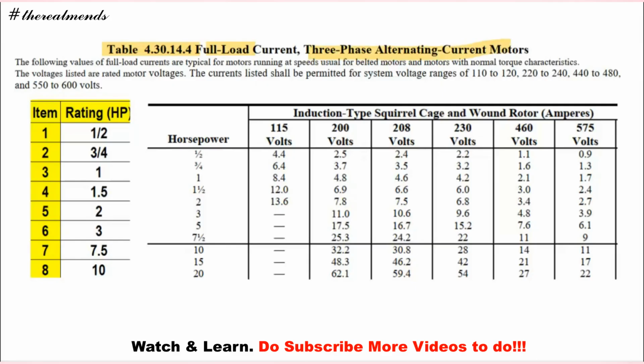So meron tayong table, this one is horsepower, so induction type squirrel cage, wound rotor, amperes. So meron tayong selected na rating ng HP natin, may 1/2, 3/4, 1, 1.5, 2, 3, 7.5 at saka 10. So assume na yung ating aircon is naka 3-phase siya, 230 volts. So it falls from this column.